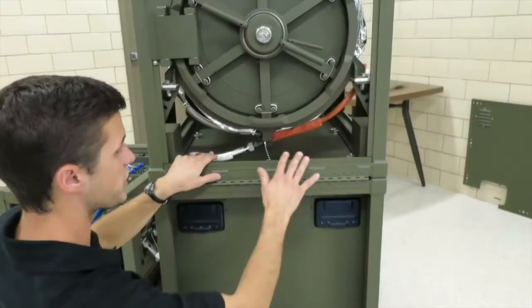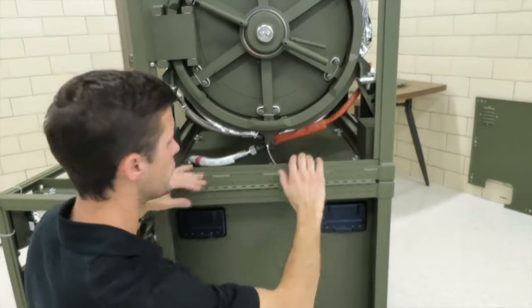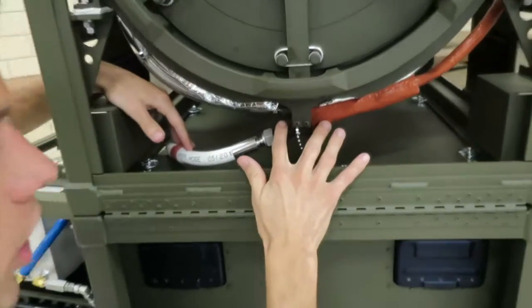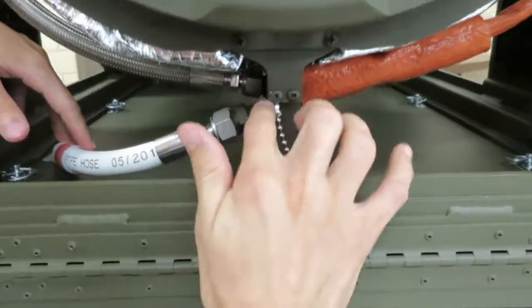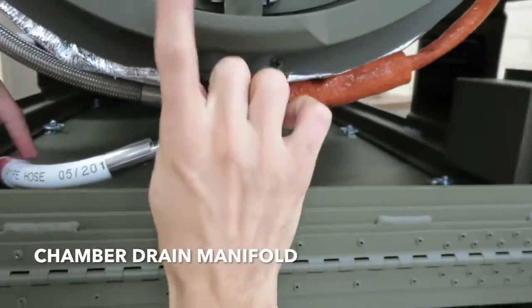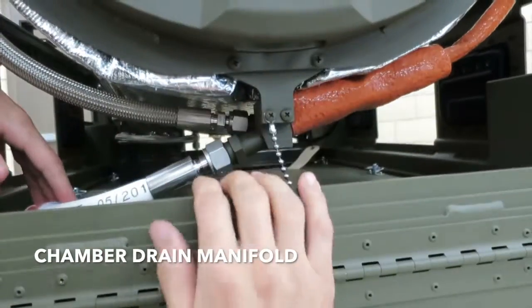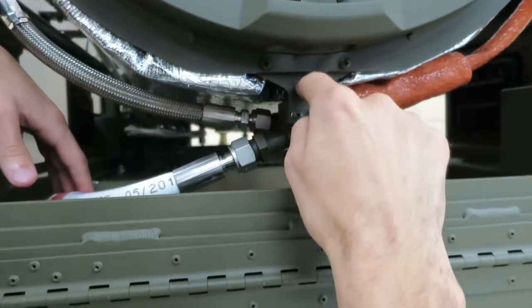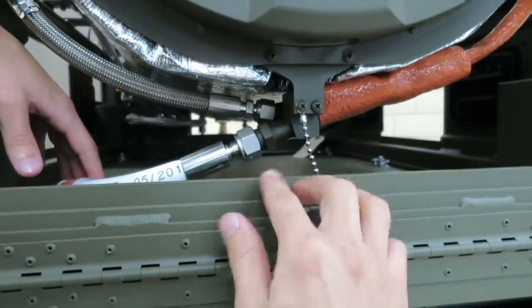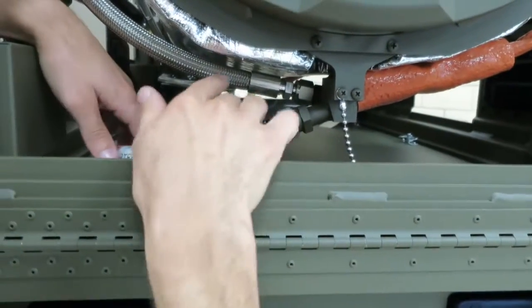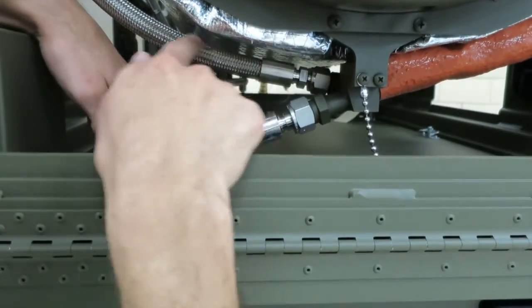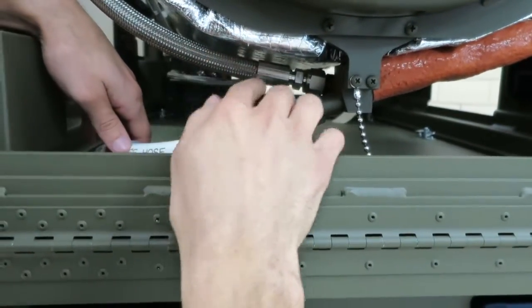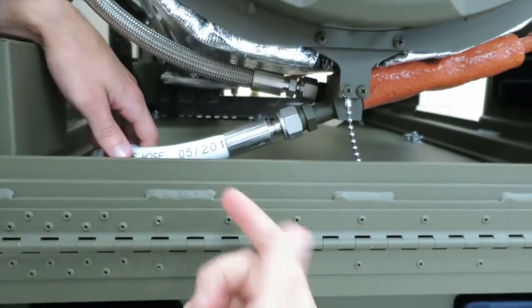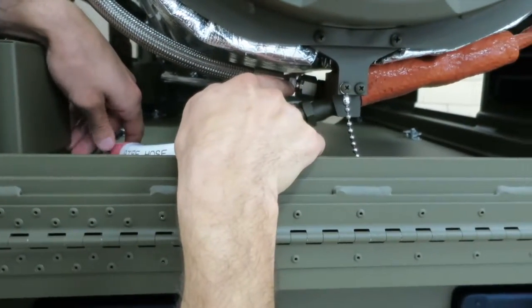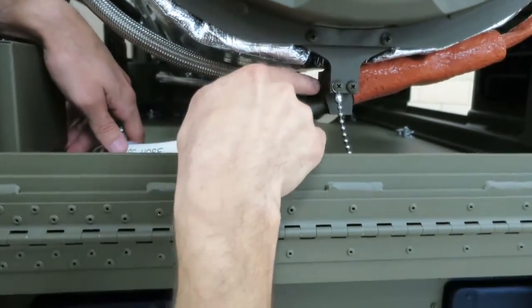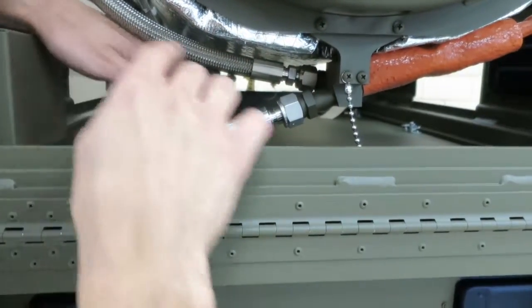So on the front of the sterilizer, with this bottom panel removed, a very important part to the sterilizer operation is the drain manifold here. So this is mounted to the bottom of the chamber. So if you open up the door and you peek into that hole, you're peeking into this manifold right here. We got three things attached to it. This hose in the back is the vacuum exhaust hose. So anytime you're evacuating the chamber of steam or air, the water recovery system is pulling that vacuum and it's being evacuated through this hose.